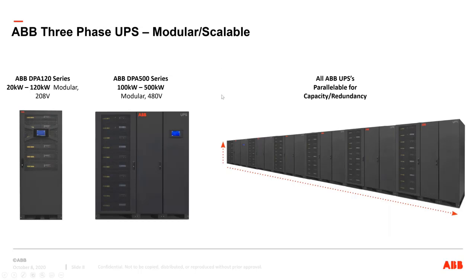legacy ABB UPSs were modular scalable type products. What that means is that the black box in the middle is a 500 kW. It actually consists of five individual 100 kW modules, or in the ABB case, they're individual UPSs. So electrically, this would be like if we took five of the TLE 100 kWs and put them in parallel. But it's not the same power unit. It's a different design altogether, much more compact. But that's the basic design of the ABB modular UPS. It's small UPSs in one frame. The frame is just holding the modules and then having landing space for the cables.